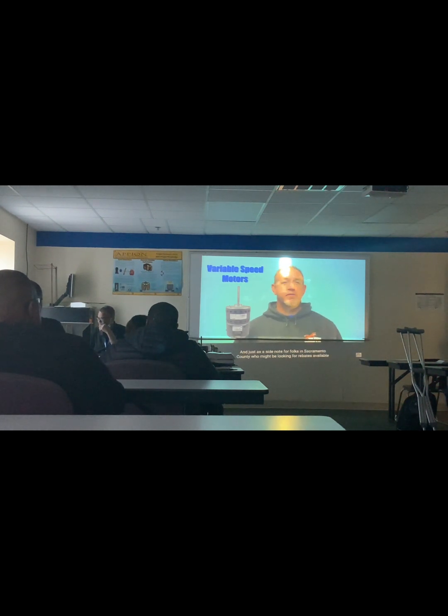And just as a side note, for folks who live here in Sacramento County who might be looking for rebates available through our local utility company, SMUD has verbiage in their new rebate structure, and this is in 2021, so double check those rebates. The new rebates revolve around furnaces and air handlers that have variable speed motors. In this case, ECM variable and ECM constant torque motors are the same to SMUD. But in the real world, when we're talking to each other about these two different motors, it's constant torque and variable speed motors. So let's expand a little bit now on the differences between those three motors.